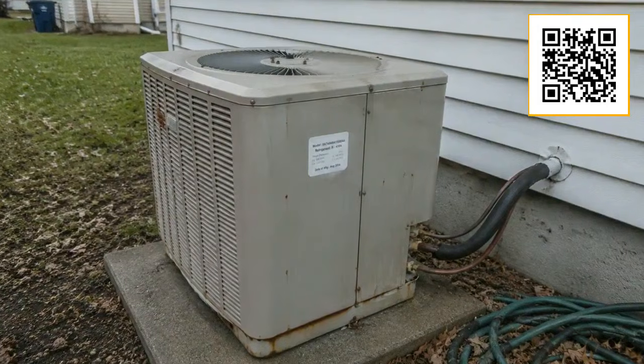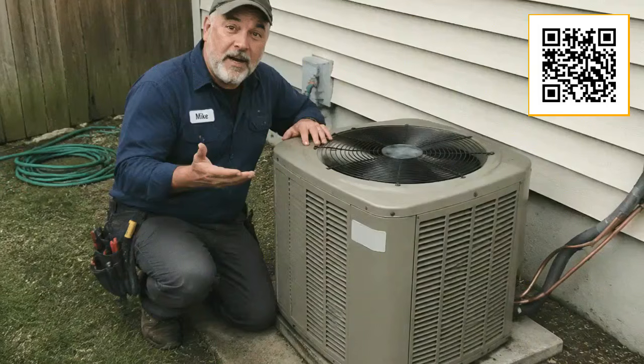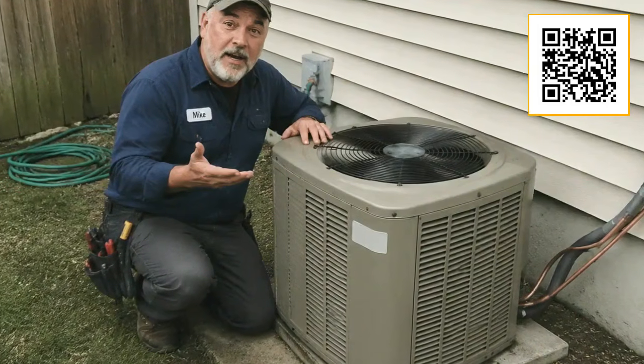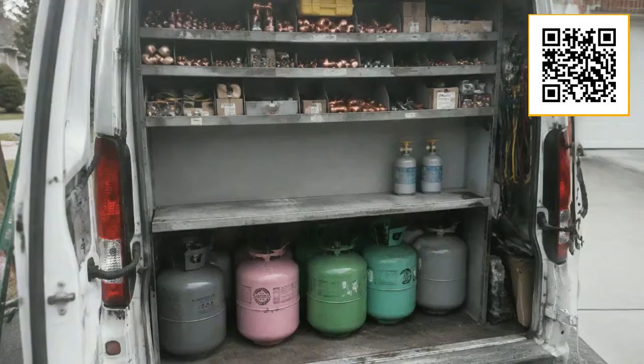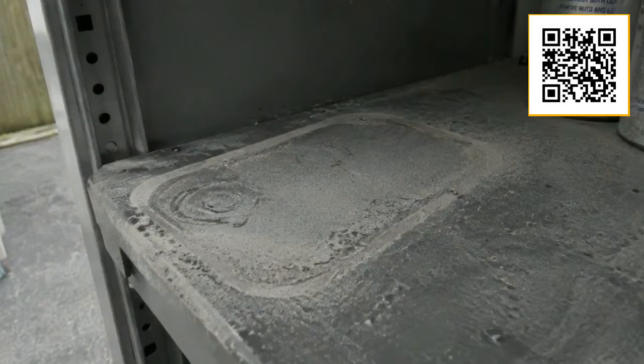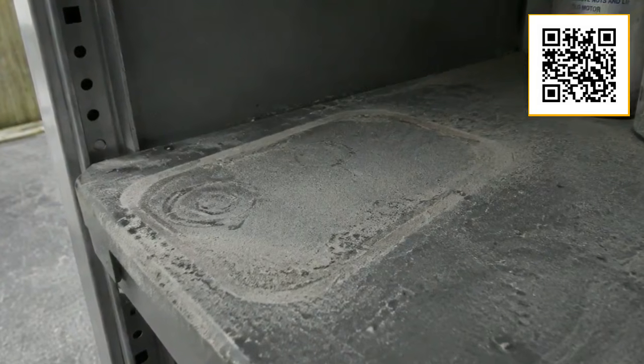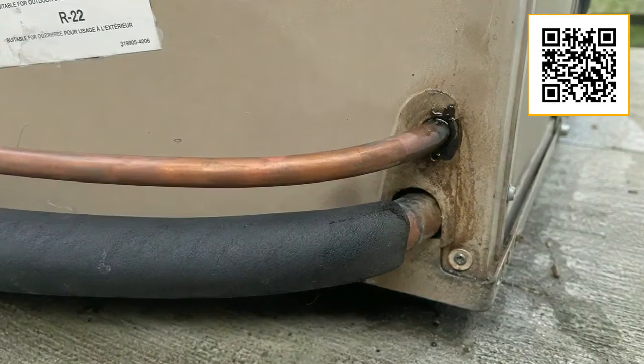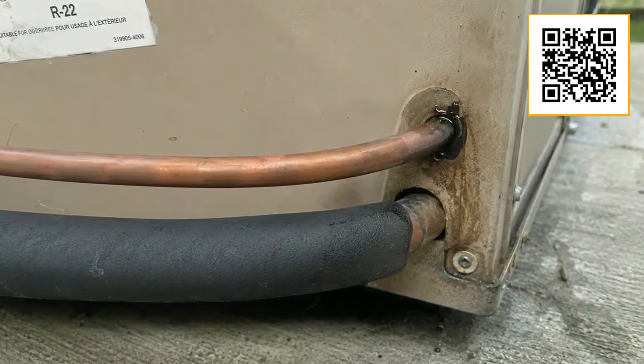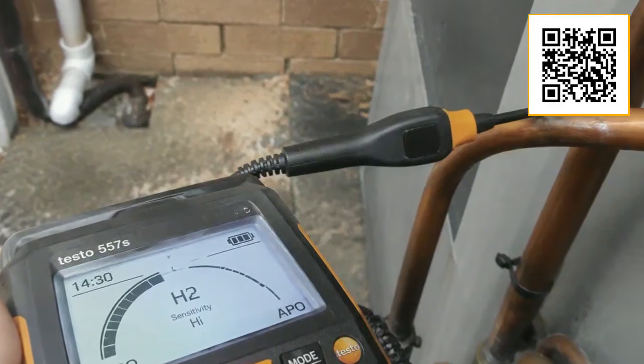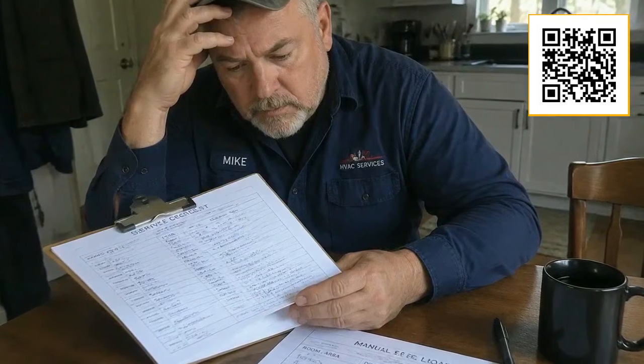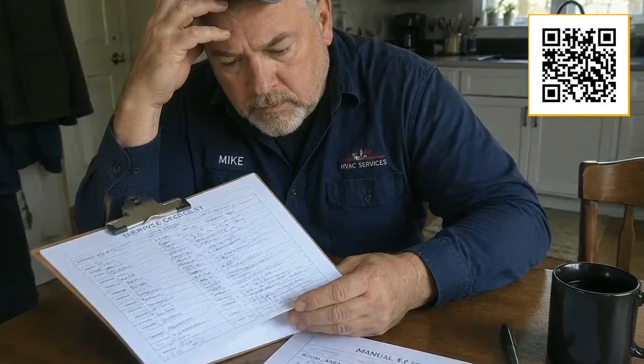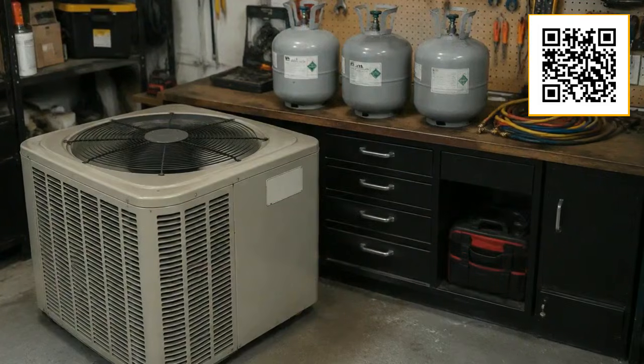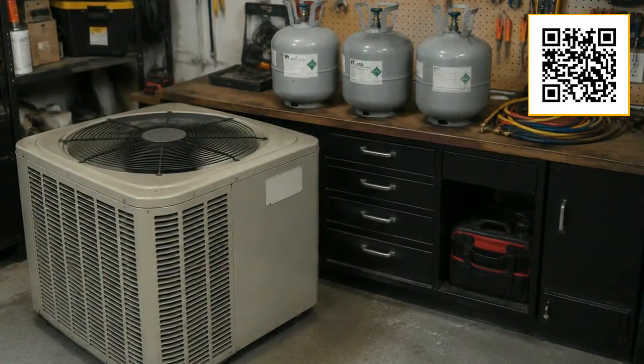Seventh on my list are older systems still running outdated refrigerant. For years, the most common refrigerant in residential AC systems was R22. It has been phased out of production, and the supply that remains is limited and expensive. If you have an older system that still uses R22 and it develops a refrigerant leak, the repair costs can be significant, sometimes high enough that replacing the unit entirely makes more financial sense. As of 2020, the EPA banned the production and import of R22 entirely, which means the only supply left is what was recovered and reclaimed from decommissioned systems.